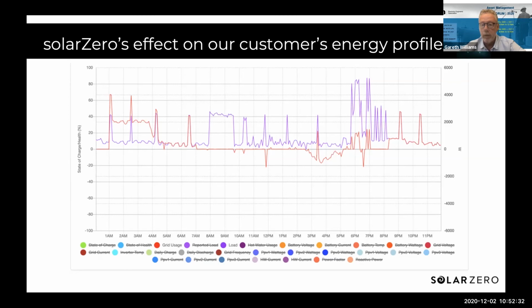There's a little bit in the evening again, a peak there around 6 p.m, a little bit of grid import, and that is purely limited by the capacity of the inverter to offset the home load. In this case, the battery reached its minimum state of charge around 8:30, so at 8:30 it was starting to import from the grid again. So again, in this case, it probably needed to be a slightly larger battery, but you can see the impact that it has on the customer's grid energy profile.